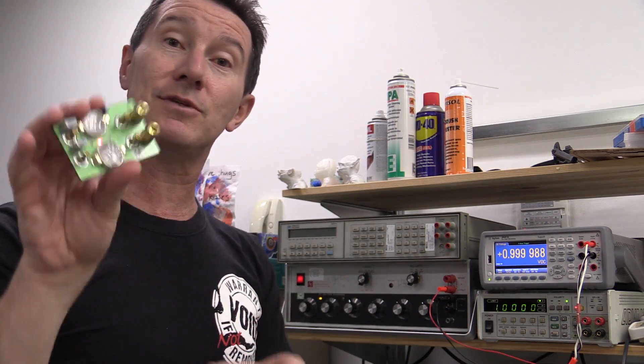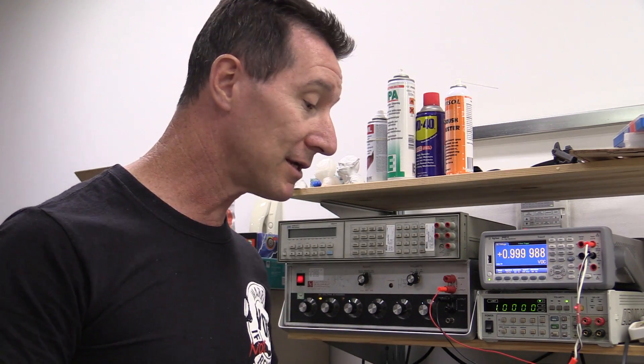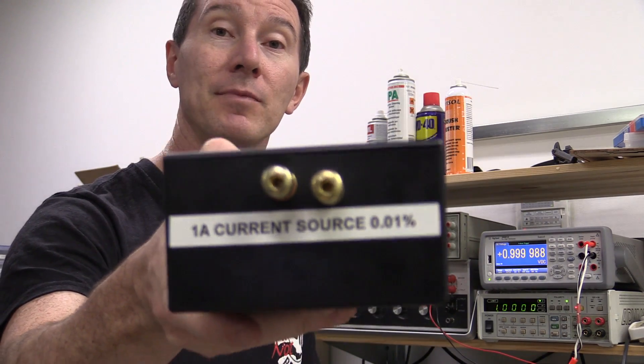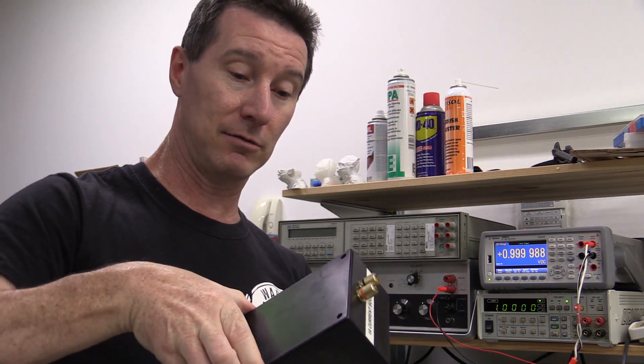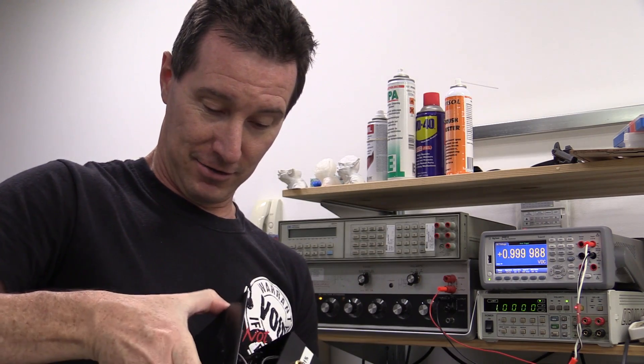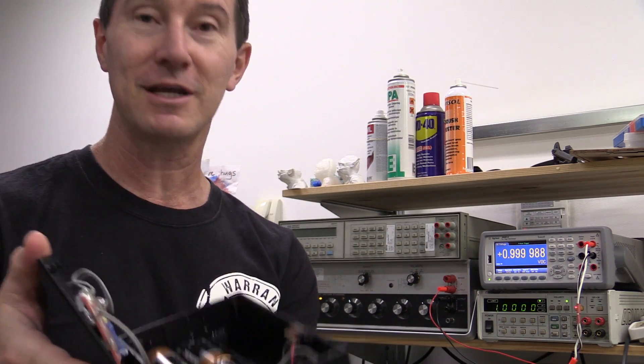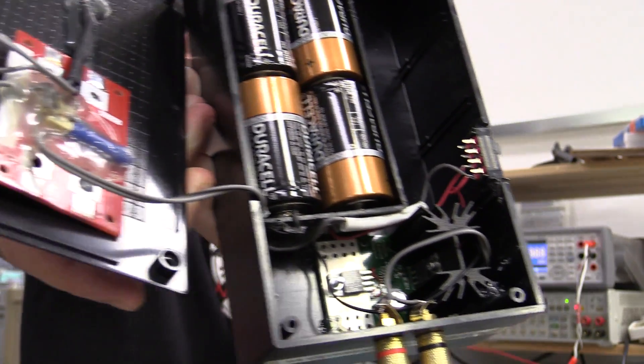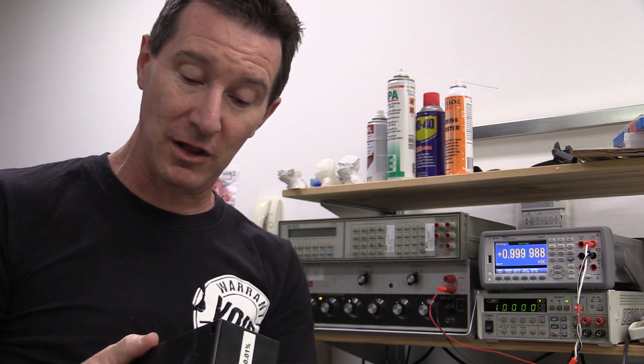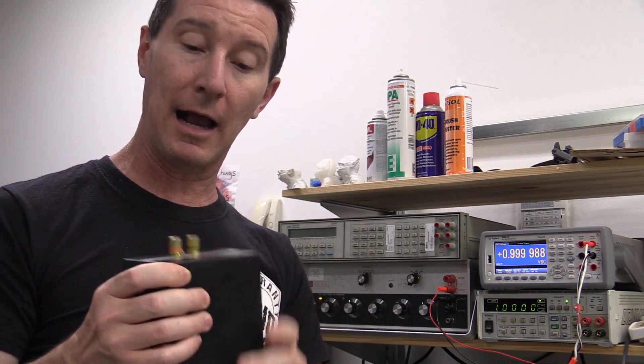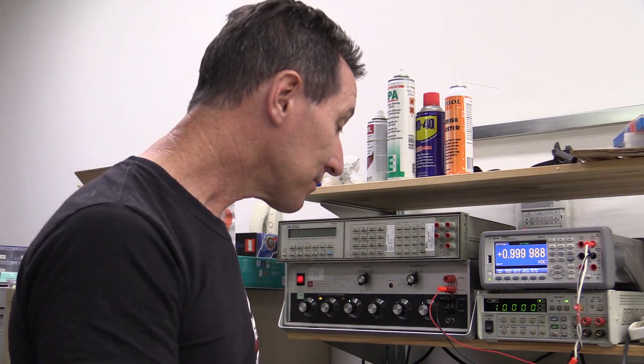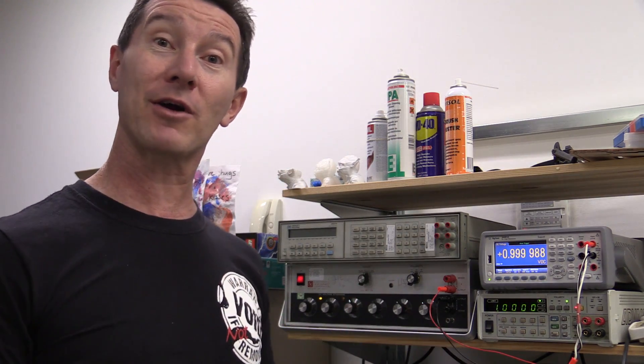I sent these to my assembly house. I don't do them here, so they're the ones who operate this. And I've got a precision current source that I've built. Have I shown inside this before? It's not pretty. There you go. But there is a small board down in there which is pretty schmick actually. It generates a really precision one amp current. So it may not look like much, but this generates the current reference for the microcurrent calibration.